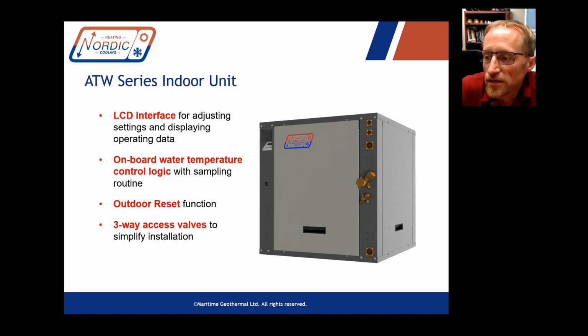So of course the air source heat pump always knows what temperature it is outside, and it can reduce the buffer tank temperature on warm days when your heating distribution system doesn't require such a high water temperature. So that's a good energy saving feature, because of course the lower the heated water temperature you can use, the higher the COP is, and the higher the capacity is in watts.